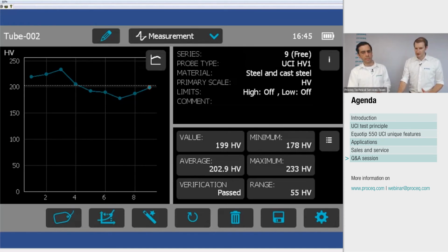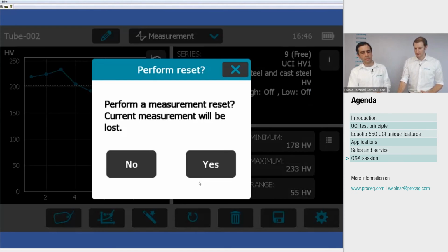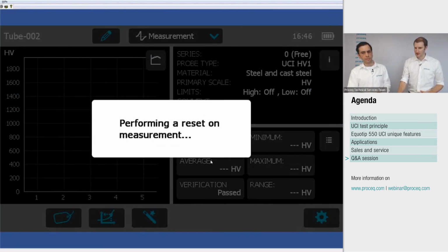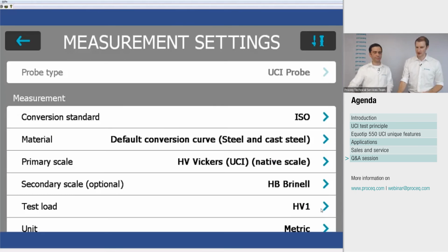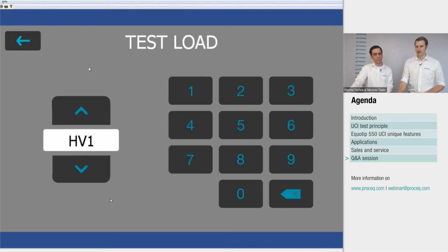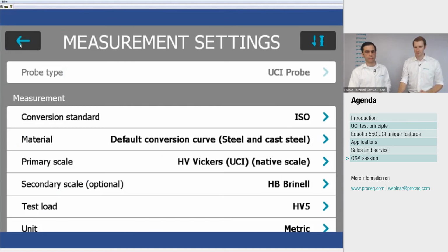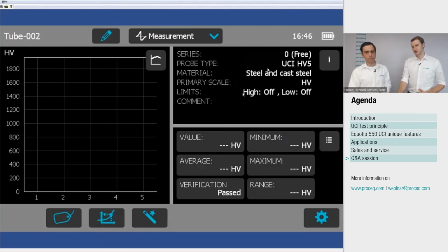But if I start a new one, now I can go to the settings here. You see the setting test load. If you tap on this field, you get this dialog where you can adjust the test load. So I can increase it now with the arrows up and down, or I can also enter the value directly over the keypad. Let's change it now for HV5. And if I go back, I see now on my measurement screen the probe type has changed, and it is now UCI HV5. So easy as that, very fast, very easy.